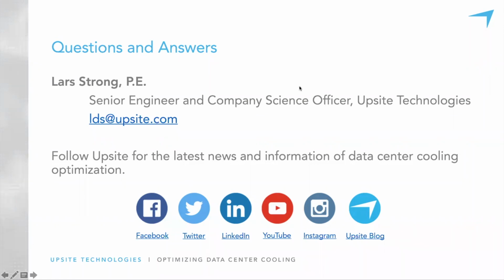Okay, the next one we got is, is there a rule of thumb or recommendation as to when to use these solutions, in row, heat exchange door, in touch, etc., regarding the kW per rack? Example, and do not consider the examples as accurate, CRAC or CRAH units, less than 10 kilowatts per rack, in row solution, 10 to 15 kilowatts per rack.